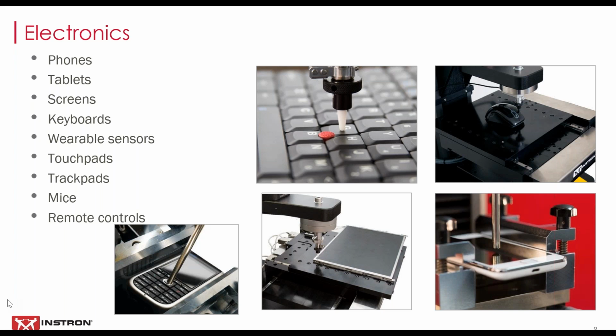So devices are tested to characterize the tactility of buttons and touch surfaces and switches. A button that's too stiff may be difficult for the customer to use, given the higher force that's required to operate it. On the other hand, if you have a button or a touch surface that's overly sensitive, that's not ideal either. A relatively small force might be enough to inadvertently engage the device.